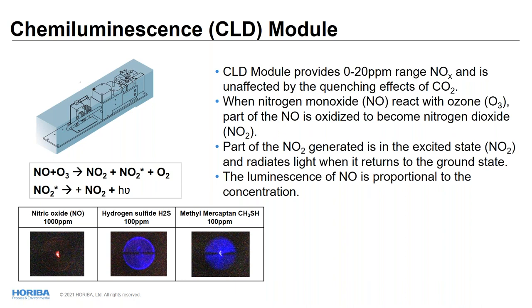Chemiluminescence works when, like I explained, NO reacts with ozone, and this part of the NO is oxidized to become nitrogen dioxide, which is NO2, right? And then part of the NO2 generated is in the excited state, and the luminescence is proportional to the NO concentration. And this is how we measure the NO.